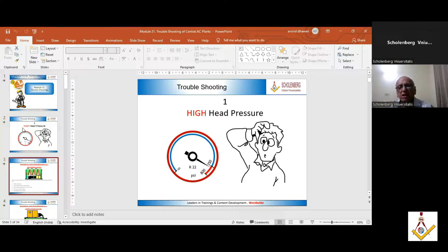First is high head pressure. That's one reason. Why that high head pressure? One, in an air-cooled condenser, you can have a dirty condenser, low airflow from the condenser fan, the air not flowing through this condenser. Non-condensing gases in the system means your refrigerant is impure, it is containing some air and some other impurities.